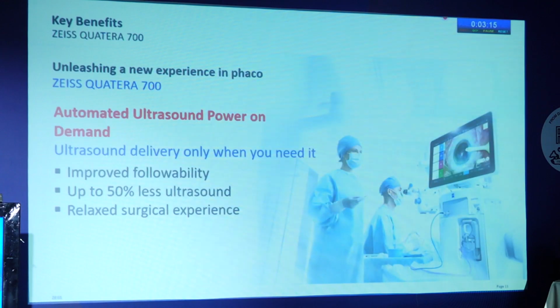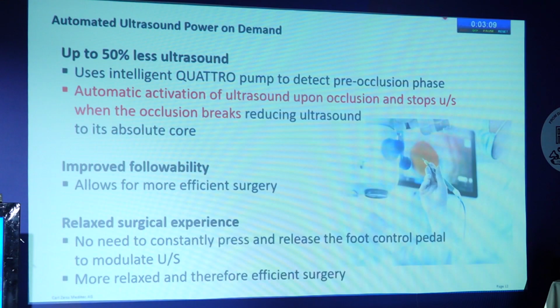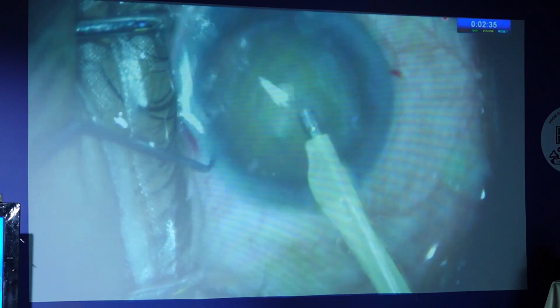And lastly, it is the automated ultrasound power on demand. So what does that mean? It helps not only to reduce the amount of ultrasound that is used, it also improves followability. The machine has an intelligent system of knowing when the phaco tip is getting occluded, and automatically the ultrasound is switched on, and when the occlusion breaks, it switches off to a minimum level. So this helps the surgeon to remain more relaxed. He doesn't have to constantly press on the foot pedal to fiddle between the ultrasound and the irrigation modes, so he can remain more relaxed throughout the surgery.